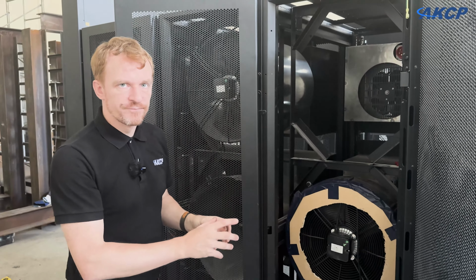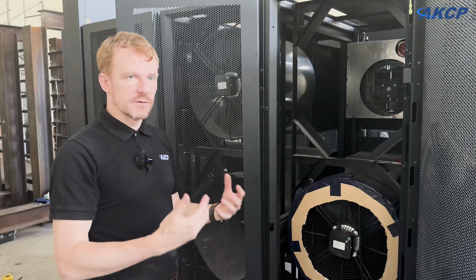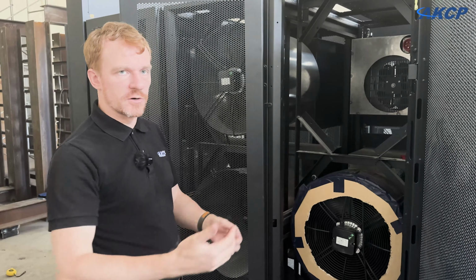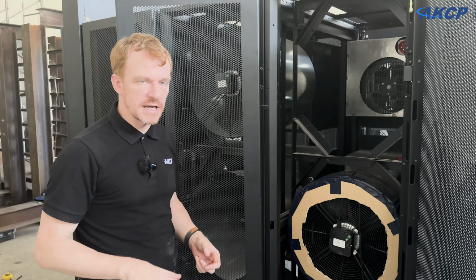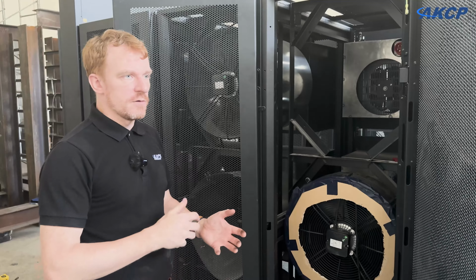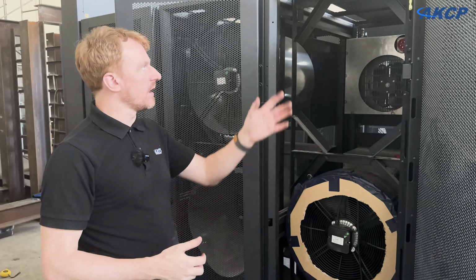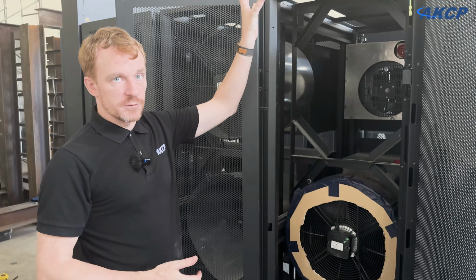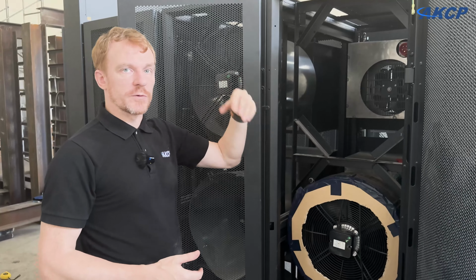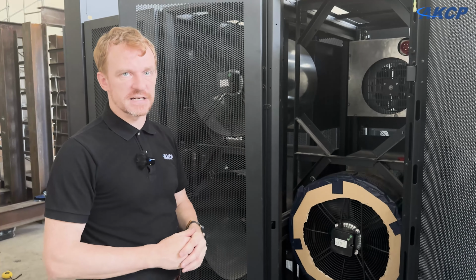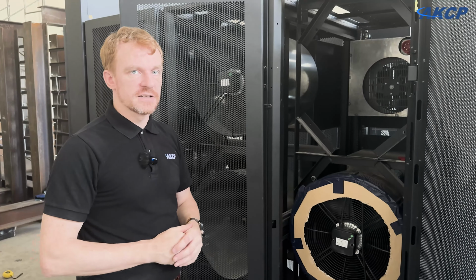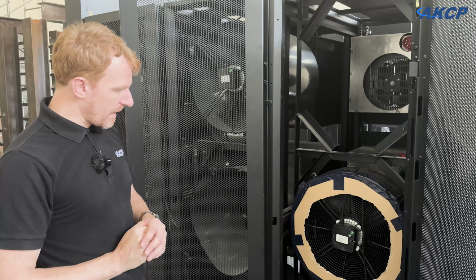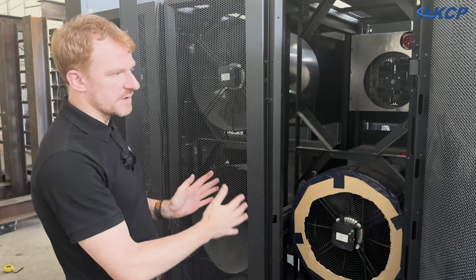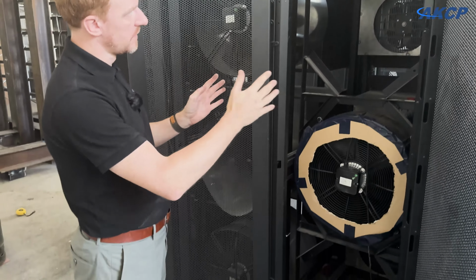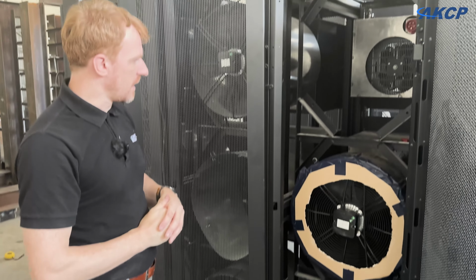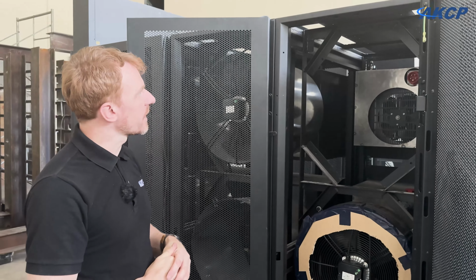have the hot air. That hot air will then either come out through one of our in-row AHUs, cooling down the room, or we'll be directing that hot air back up through some ductwork to our fan wall, or through our overhead heat exchangers that we've discussed in some of the other videos that we've been doing. So that's basically our setup. We have 20 racks like this to set up and fabricate.